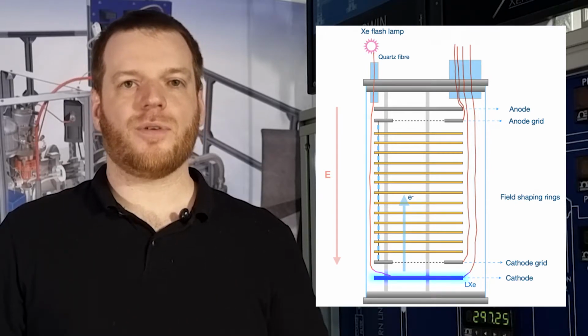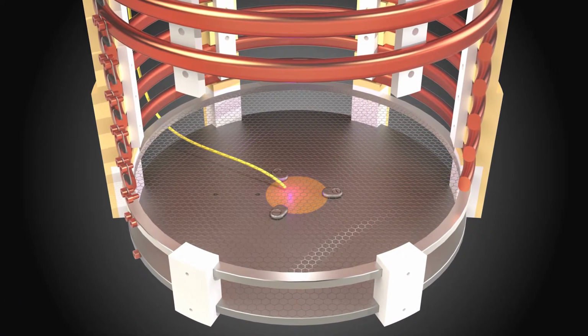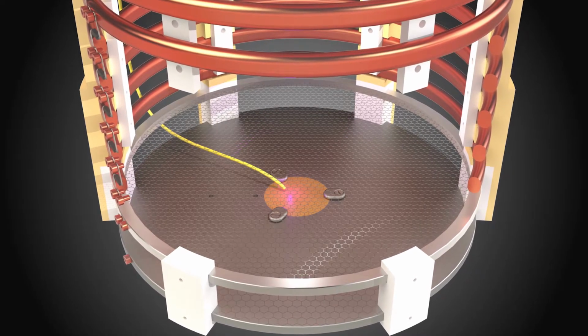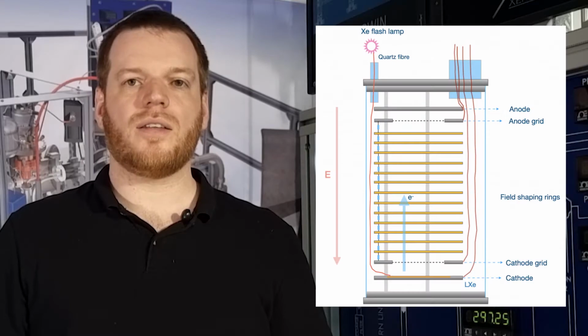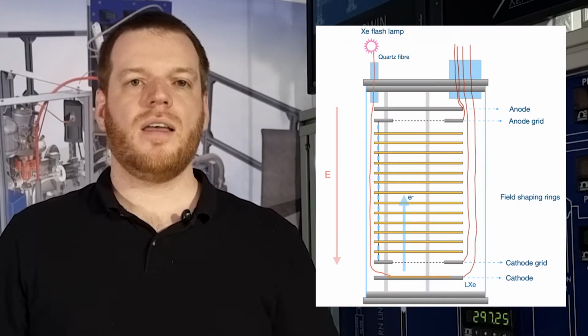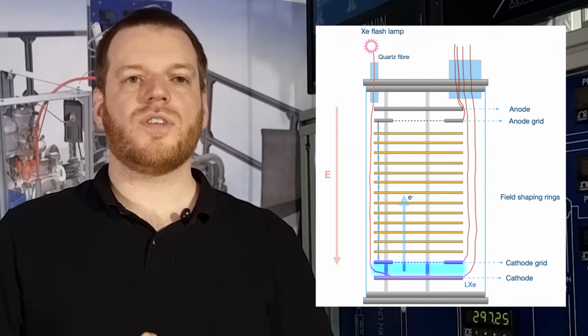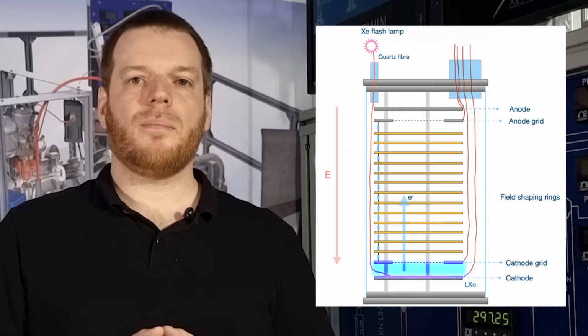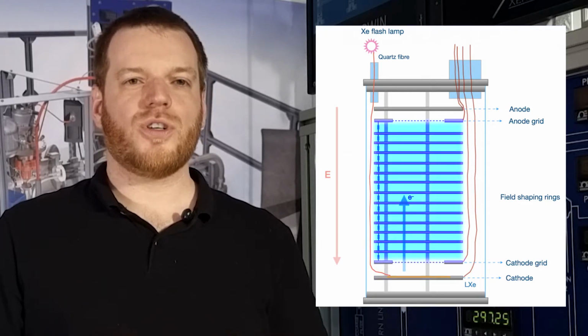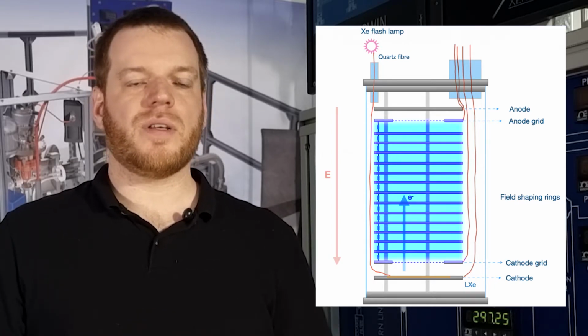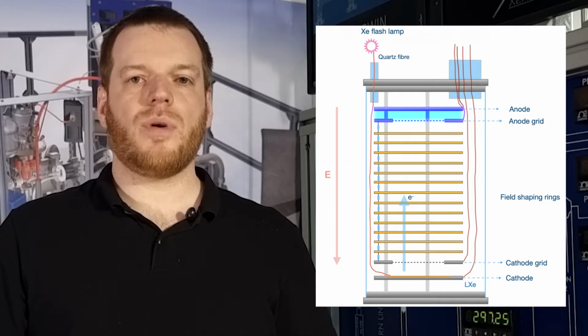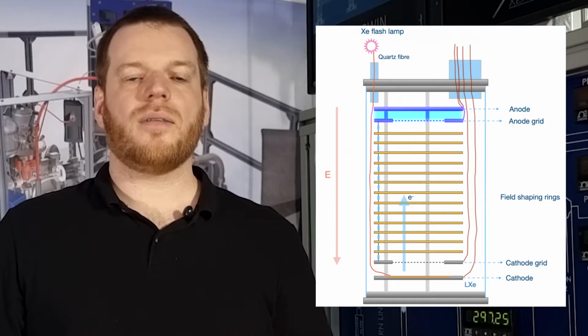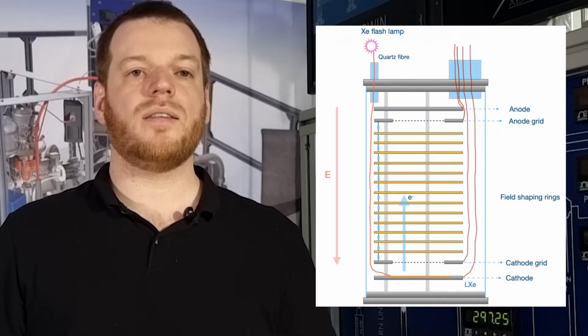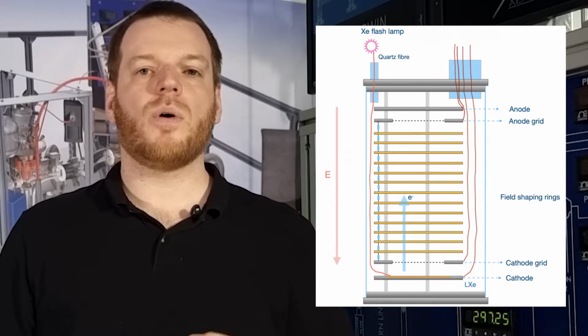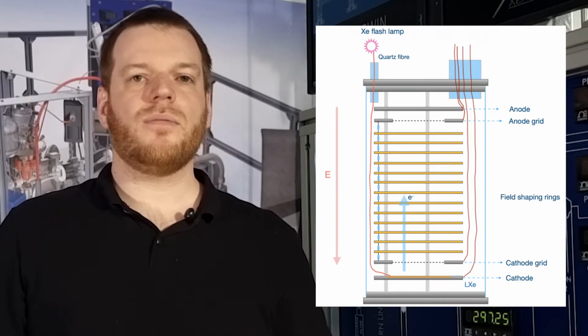First, electrons are produced by a photoelectric effect on the photocathode at the bottom by flashes of UV light coming from a xenon flash lamp. The released electrons are drifted towards the anode at the top, traveling through 3 regions. In region 1, the drift of the electron produces an induced current on the photocathode, read out by a charge readout. In region 2, a portion of the drifting electrons is absorbed by electronegative impurities. Finally, the electrons reach region 3, where they induce a current in the anode, again read out by the charge readout. The ratio of the charge read in the charge readouts can then be used to calculate what we call the electron lifetime. This can in turn be directly interpreted as a measurement of the xenon purity level.